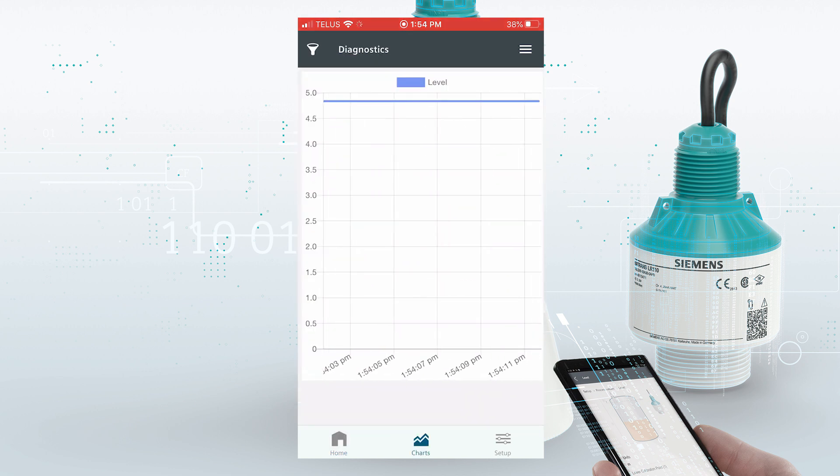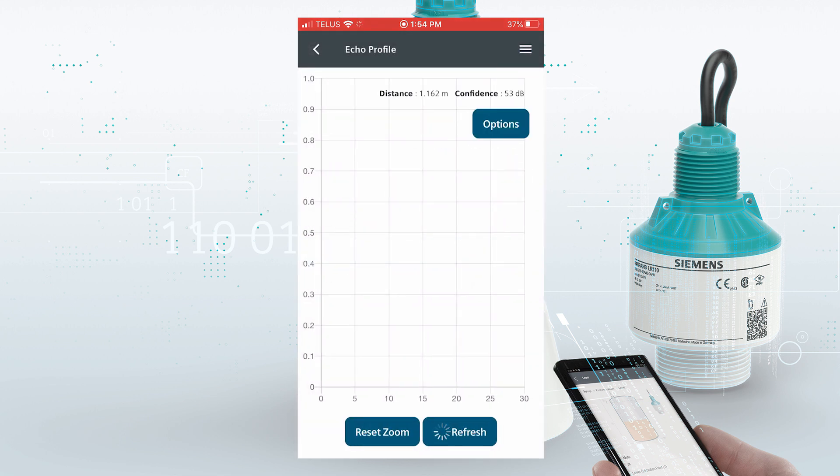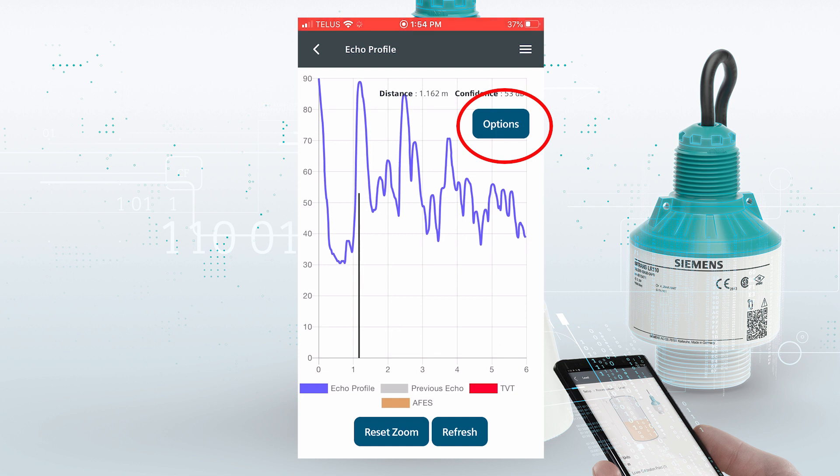We want to look at the measurement trends. We have five different trends that could be shown simultaneously, and also we could view the echo profile within the chart setting. Under options, there are a few choices where we could show the TVT or we could show the auto false echo suppression curve. But obviously this is a very, very healthy signal — reflection from the application here at a distance of 1.162 meters, very strong confidence value of 53 dB.